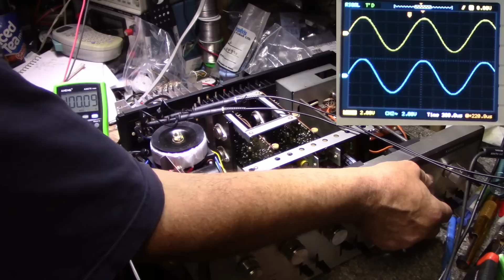Let's go up, here's clipping, full power. So 100 volts going in from 102, we only dropped 2%. That's very good for stability. If you go from 0 idle, 2.2, 2.1, to full power, you only lost 2% of your voltage, which is good. Let's get this up to full power. We're at 170 watts here, 1.7 amps, 82% power factor. Everything looks really good, I'm really pleased with this.